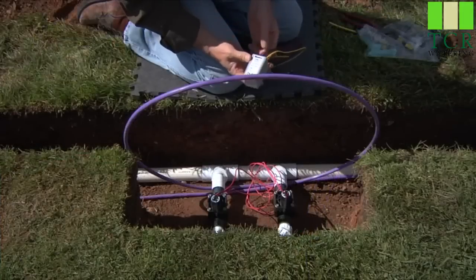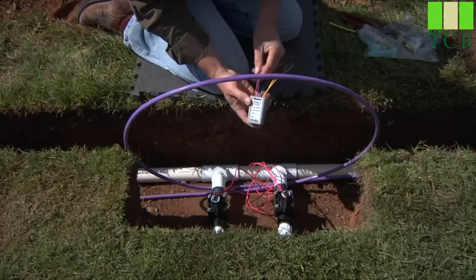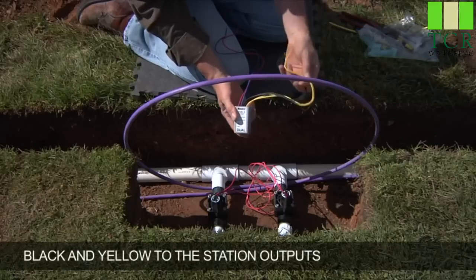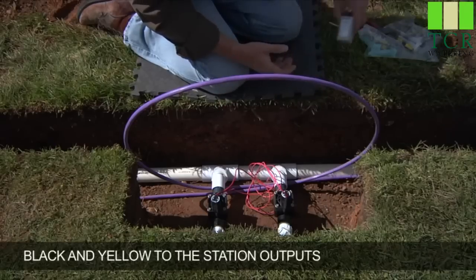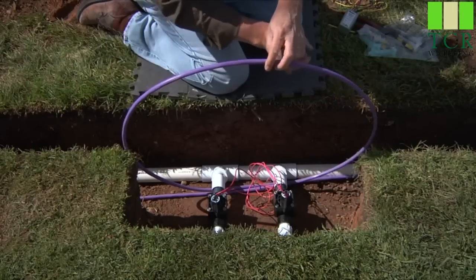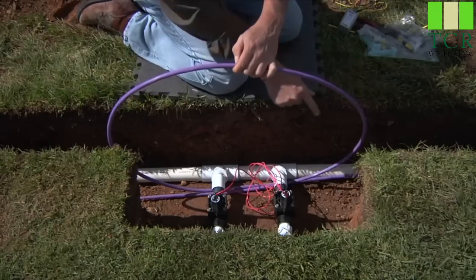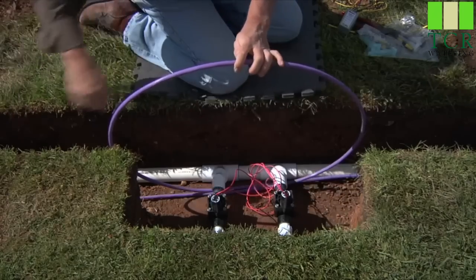Here we'll be installing a dual two-station output decoder. We have the red and blue wires that will attach to our wire path, and we have the two blacks and the two yellows which are the station outputs to the solenoids. You'll start by having the ID wire looped up for about five feet of extra wire above ground to work with, or about a meter and a half. You can see that the ID wire comes into this valve box, loops up, and continues on downstream.